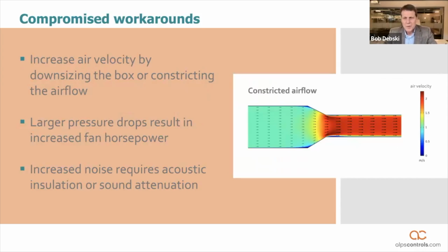Compromised workarounds. So if one of the problems with a conventional air terminal is poor airflow measurement at low velocities, what's one of the easiest solutions? Increase the velocity. Typically, the airflow velocity has been increased by constricting the airflow. And what happens when you constrict the airflow? You create resistance. When you create resistance, you create pressure drop. And when you increase pressure drop, you also increase fan horsepower. So even though that was a solution to get more accurate airflow, it has a whole host of other compromises. You also have the additional problem of increased noise generation caused by those higher velocities in the duct.